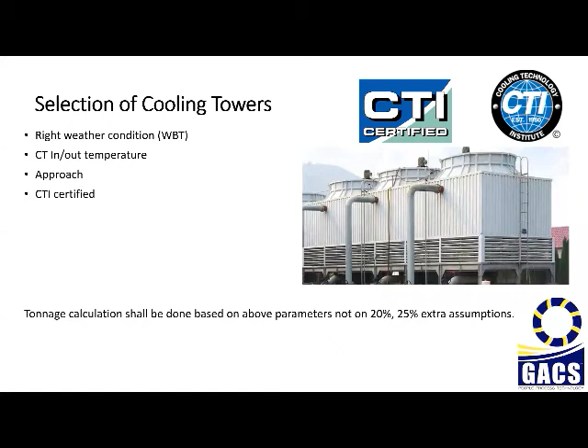Now there is a myth. We always think that if we run the chiller at a lower load, it will be an efficient operation. Yes, it will be an efficient operation, but not that much. Second point, instead of running the chiller at lower load, if the chiller is running at 100% load, but we are providing cooler water, a lesser cooling water entering temperature, then it will save much more energy as compared to running a chiller on part load. So this can be possible.